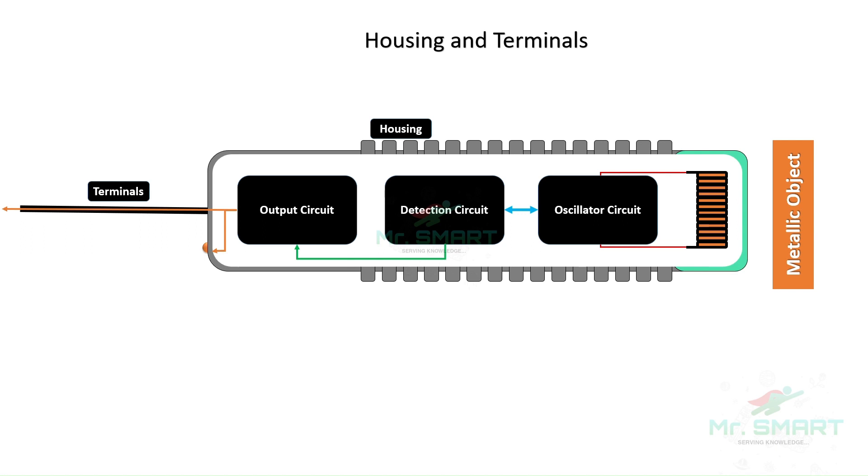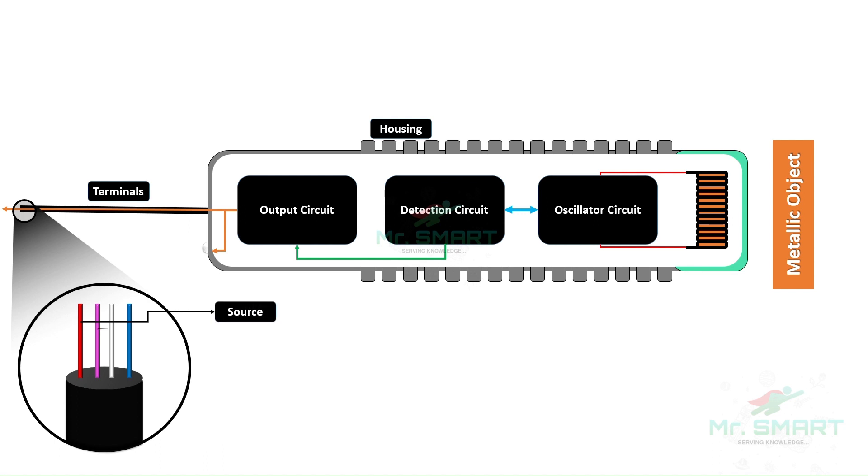Connector or terminal is the part through which the sensor transmits the signal to control systems such as PLCs or relays. Typically, the terminal or connector consists of four or three wires. In a four-wire connector, two provide signal and two provide power supply for working of internal components.